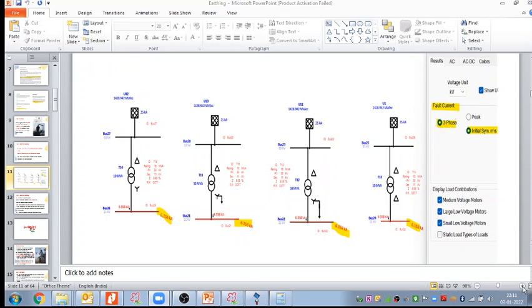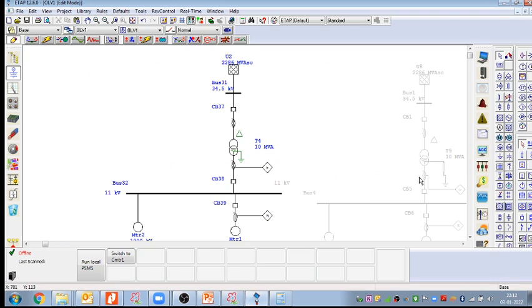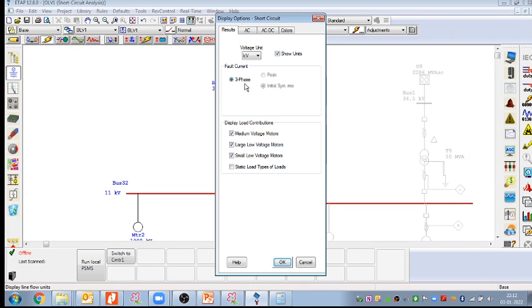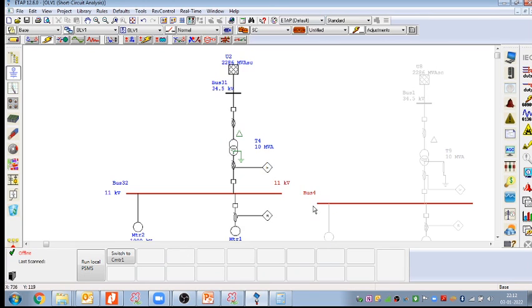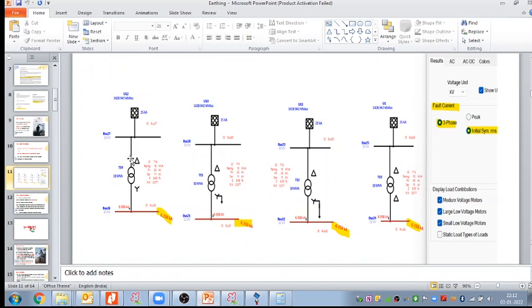Okay. Yes, the case is that we have taken four cases. Case 1: we have taken a 33 by 11 kilovolt, 10 MVA transformer, delta star, and we have done the three phase fault current. If delta star, the value is 6.35, it is not changing. If the star is earthed, the grounded system, again the fault current remains the same, 6.358 kA, nothing changes. If I do delta star with the NGR, in that case also, when we run the simulations, the result is the same, nothing changes in the three phase fault.